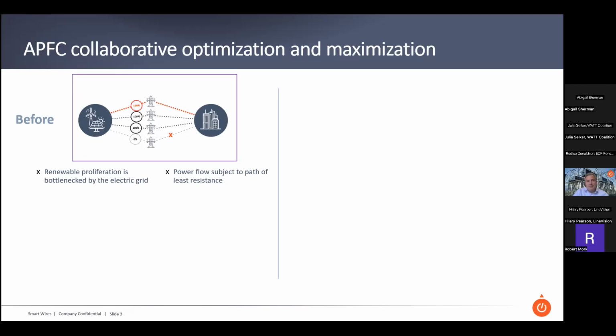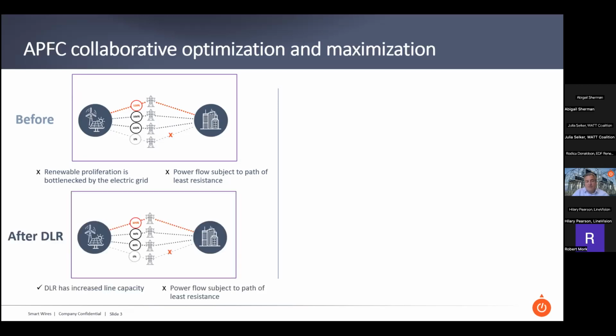So you have an issue - where are we going to push the power to if we were to put advanced power flow control on? However, if we use another technology - Robert will talk a bit about this after this presentation - we put in dynamic line rating. Now we can see there's an increase in rating at various points across the year, which would effectively reduce the overload on that line. So it's gone from 120% to 105%, and it's also reduced the other two lines as well. You still haven't resolved the issue in its entirety, but you have made a marked improvement.